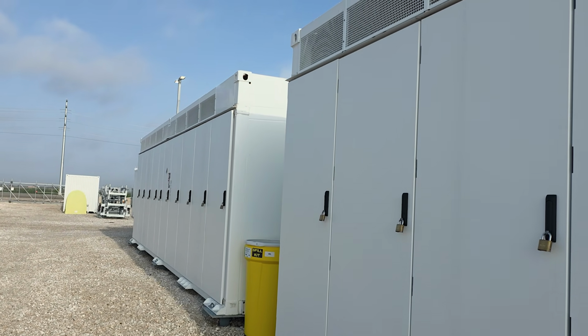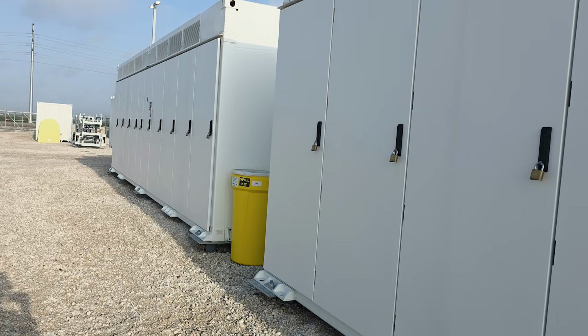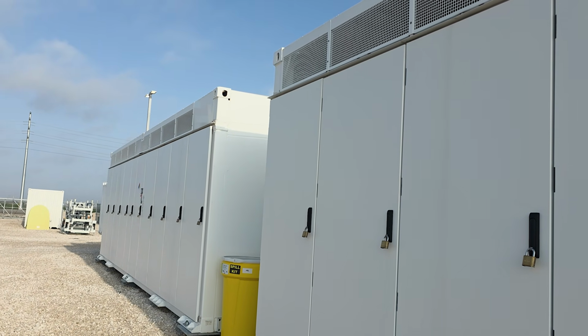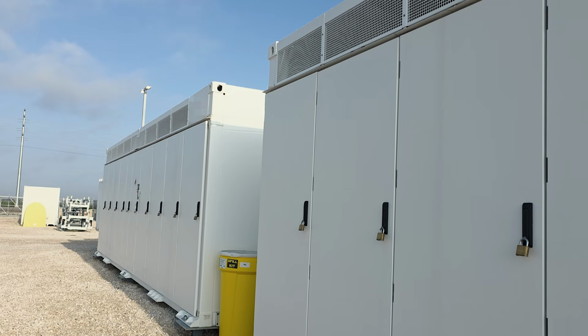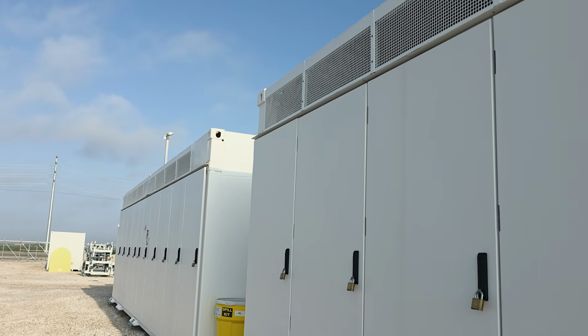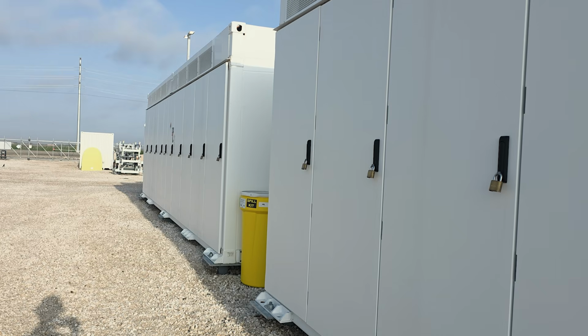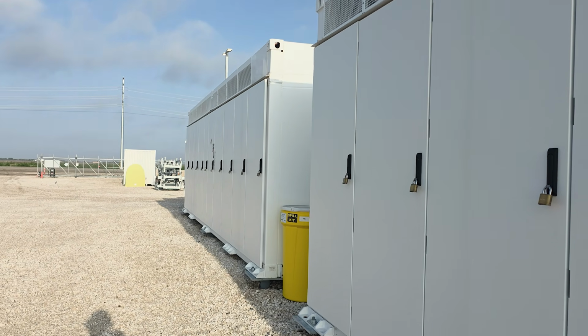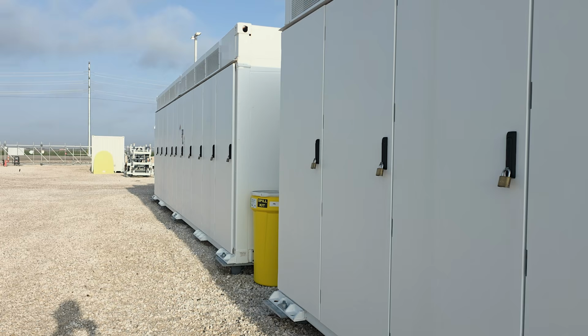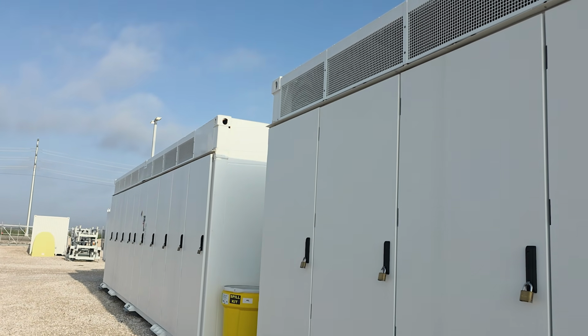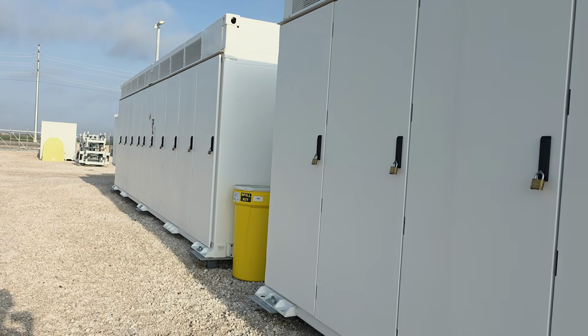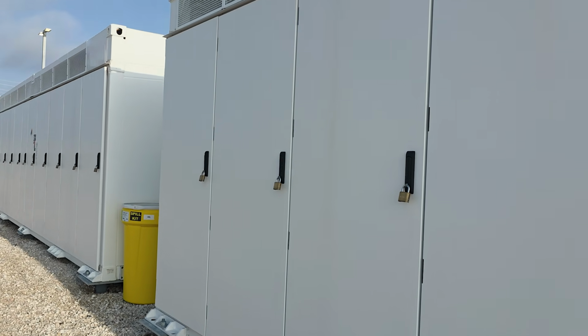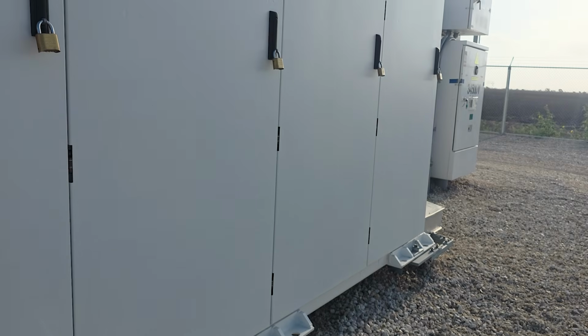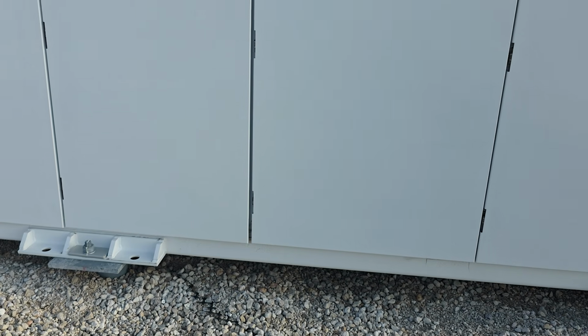But inside of these doors are just stacks of batteries. They kind of come in kits to where they will slide in and slide out, kind of like a breaker where you can rack it in and rack it out. Same type situation. You bring almost like a cherry picker out here in front of the door, and you pull them out and you lift them up with the cherry picker and you can replace them. So it's kind of like a modular system. I don't recall how many batteries are in each of these, but it varies per manufacturer, right? But batteries. I'm not going to show some of the labeling. More batteries, and in this particular case, the inverter is right here in the middle between these 2 cabinets.